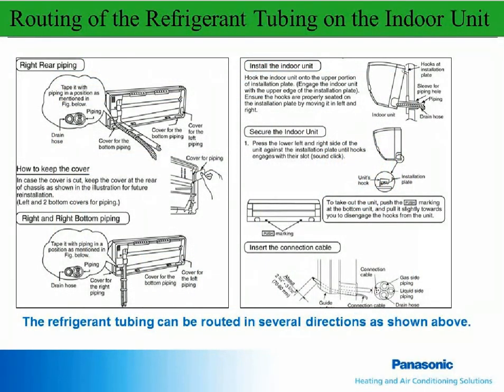The refrigerant and drain lines on the indoor unit can be routed through the left or right side or the left back or right back. This gives you several options when choosing a location for the indoor unit. If the indoor unit is mounted on an outside wall and the outdoor unit is directly on the other side, then exiting through the right and back of the unit would be easiest. This would also allow tightening and leak checking of the flare connections outside.